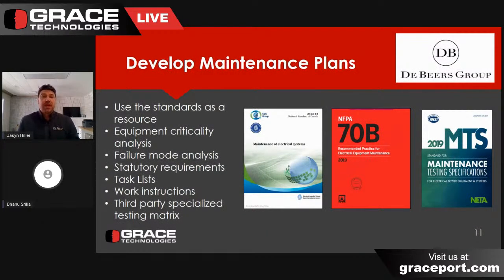Developing maintenance plans: we had unplanned outages that caused significant interruptions to mining operations due to flooding. When the power goes out, the water floods very quickly. We found that when we opened equipment, there was diesel particulate that had allowed the high voltage to track between the phases. It was obvious this had been going on for a while before we had a fault causing the outage.